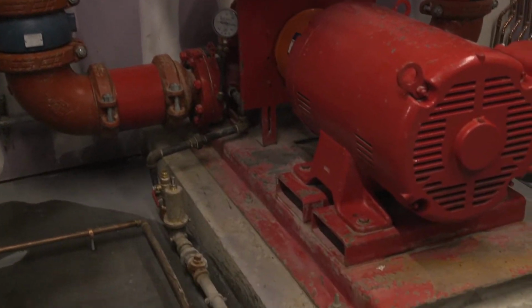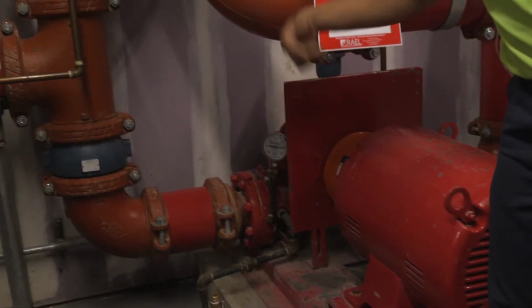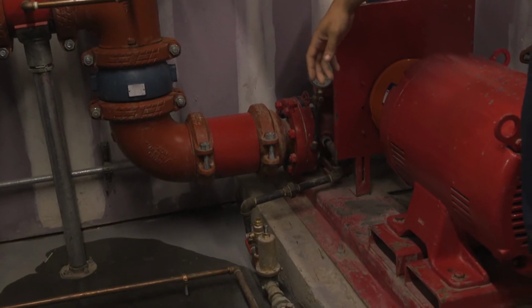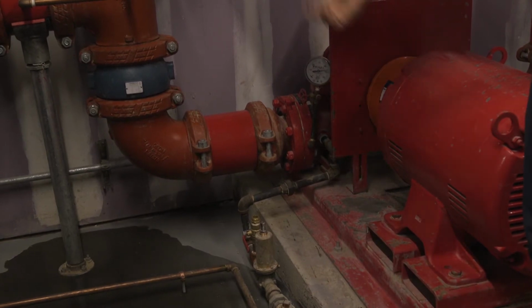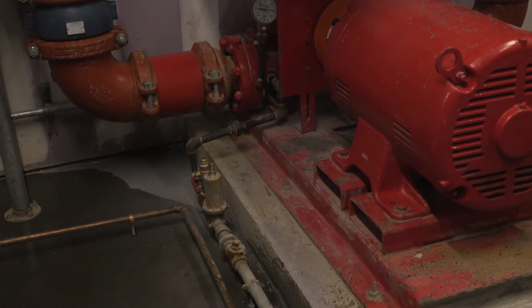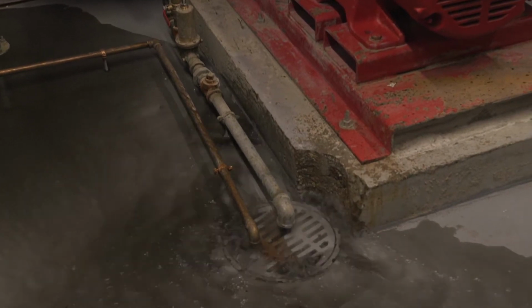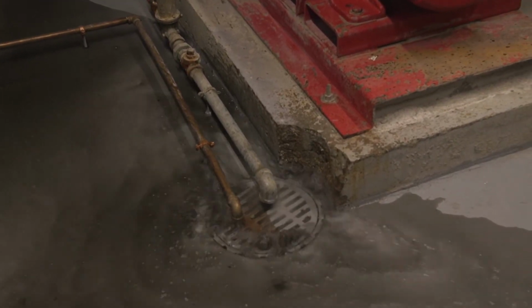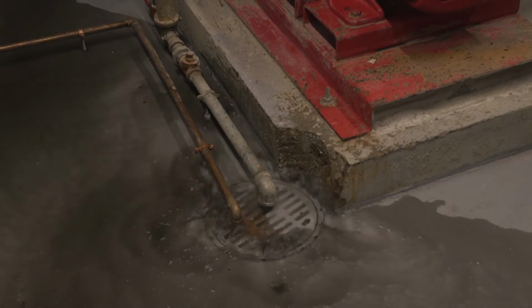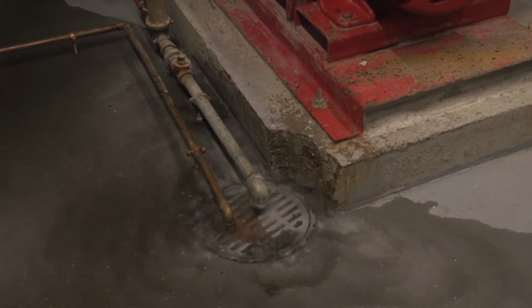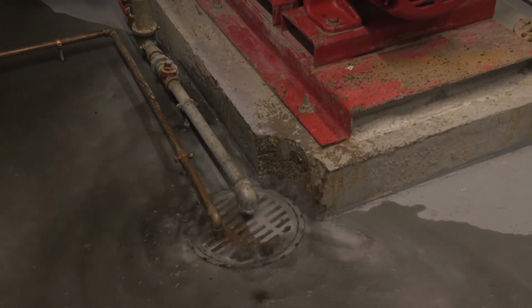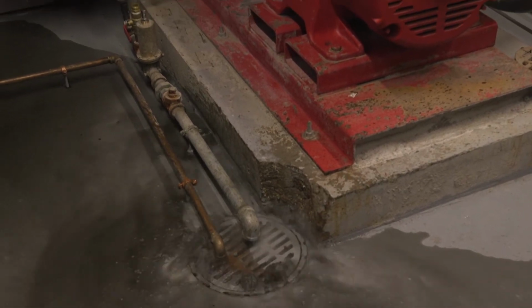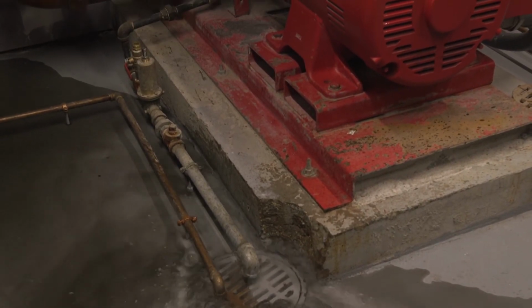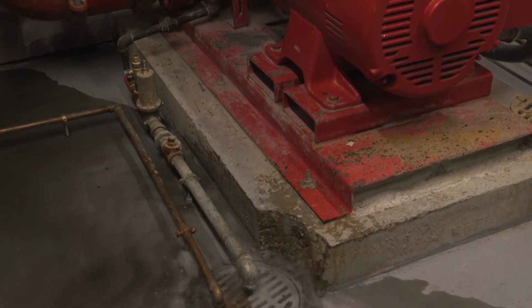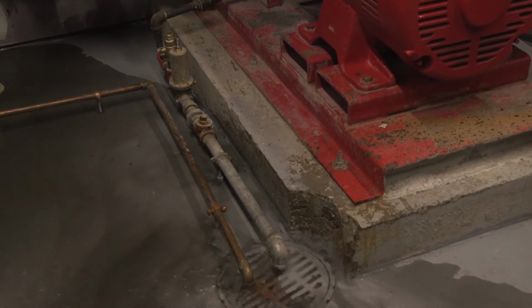So running, you're going to see the volts are going to completely stay the same. That's your casing relief valve opening. Like I said, it's for cooling. So it's going to constantly dump water to keep the pump from overheating. On main relief, everything's pretty loud, so everything should stay the same. Amperage is flowing about the same. Now we're gonna stop the pump. Push the stop button one time, and the pump is gonna slowly stop down as well.